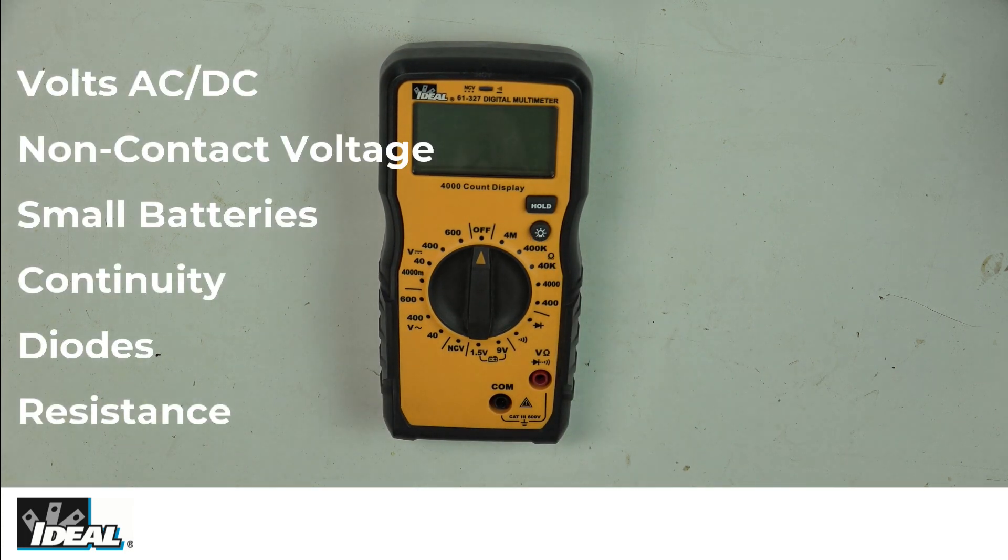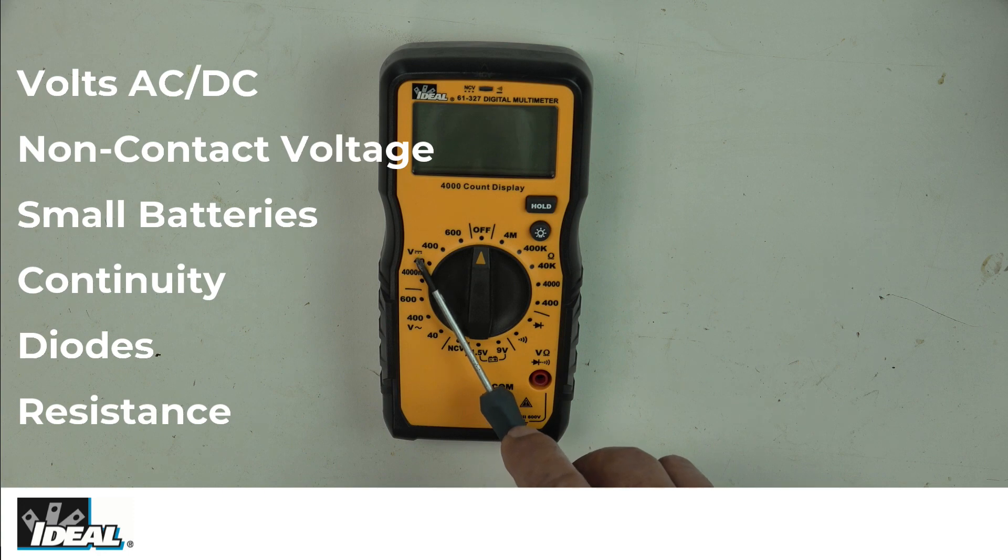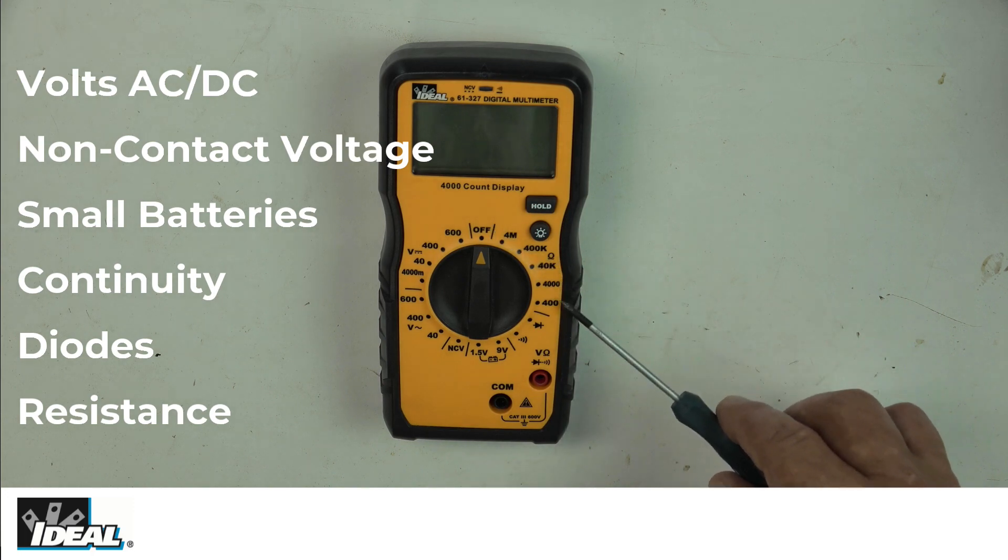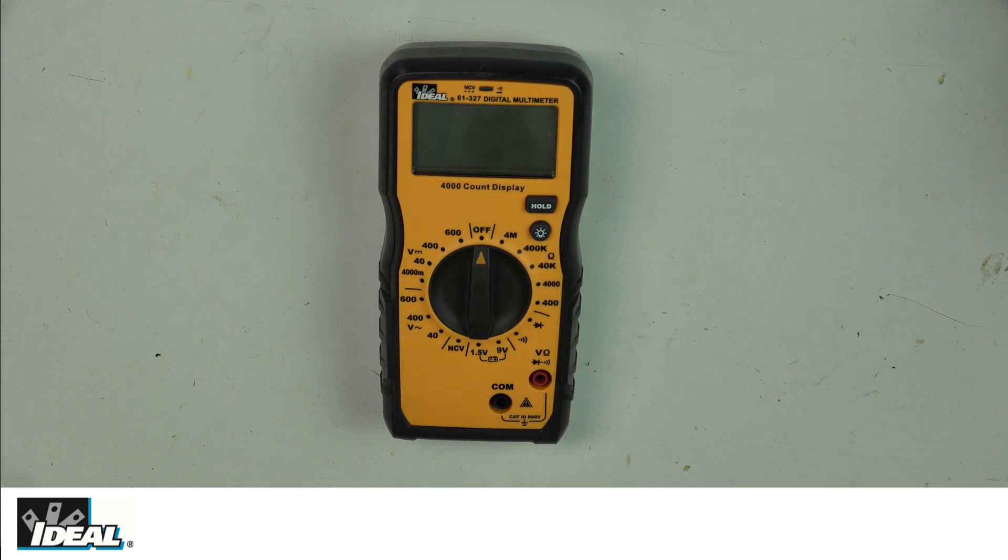I'll point out the different functions of the tester. Over here is volts DC with ranges of 400 millivolts, 40 volts, 400, and 600 volts DC. For AC, we see 40 volts, 400, and 600 volts as ranges. The tester has non-contact voltage sensing capabilities. There are settings for small 1.5 or 9 volt batteries. The audible symbol is for continuity when measuring motor windings or switches. That symbol is for a diode. And all of these are for measuring ohms or resistance: 400 ohms, 4000, 40,400, and 4 million ohms.